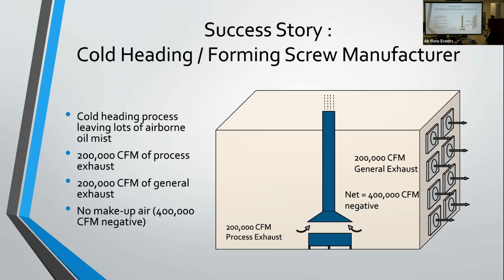So the contractors first installed a few general exhaust fans on the building to try to fix the problem. That didn't fix it. They installed more the next year. That still didn't fix it. They ended up with 200,000 CFM of general exhaust to try to fix their problems, plus the 200,000 CFM of process exhaust they already had. So they were at negative 400,000 CFM in that space, which is concerning.